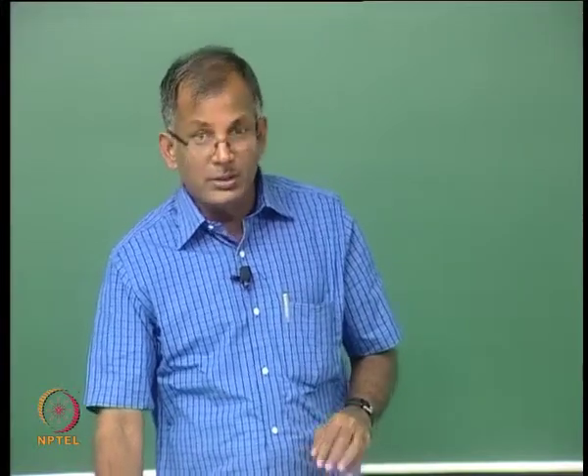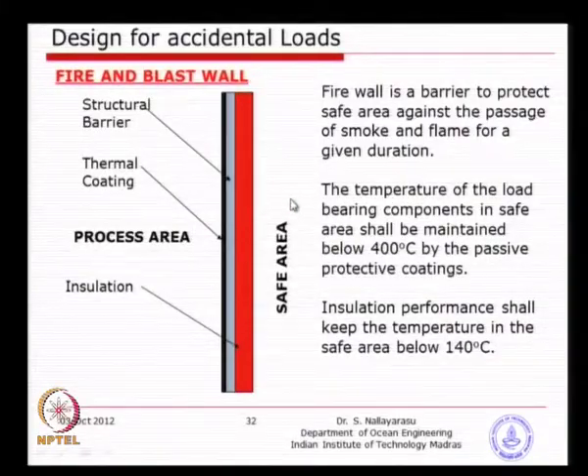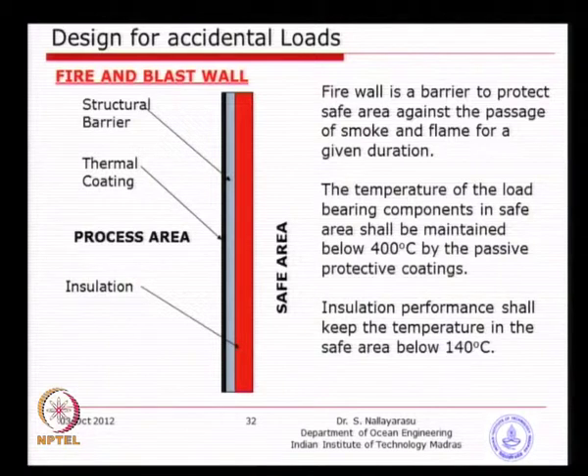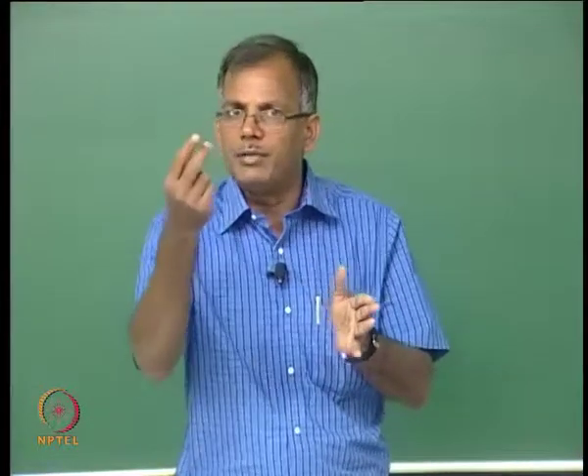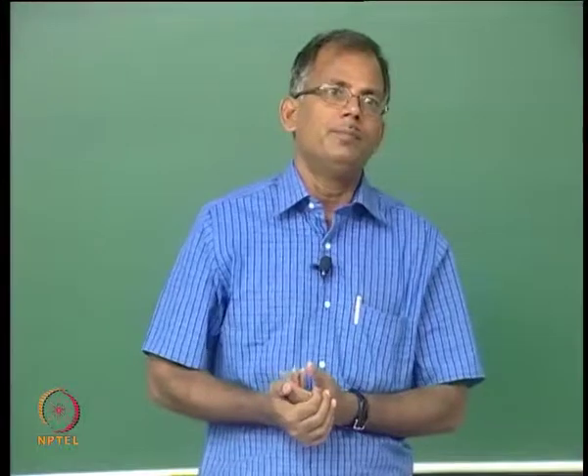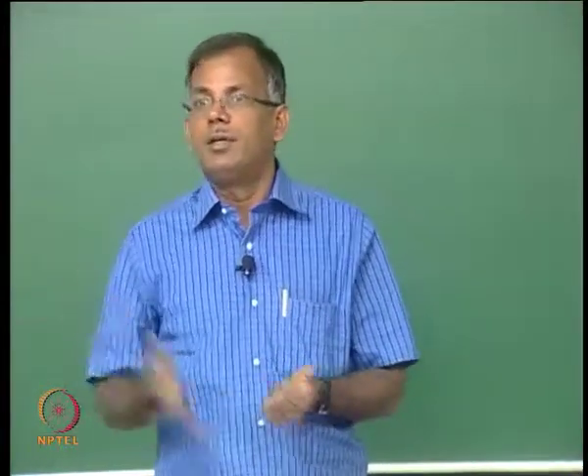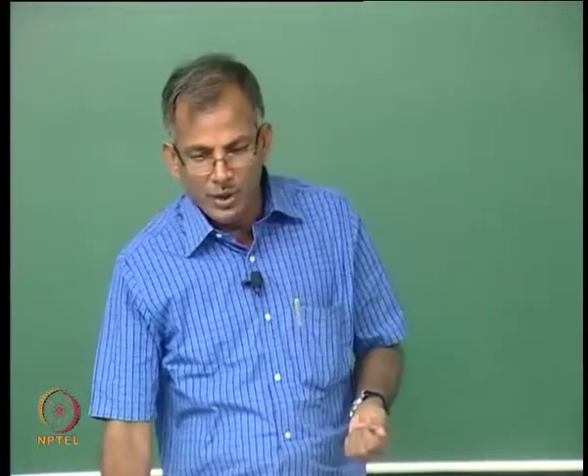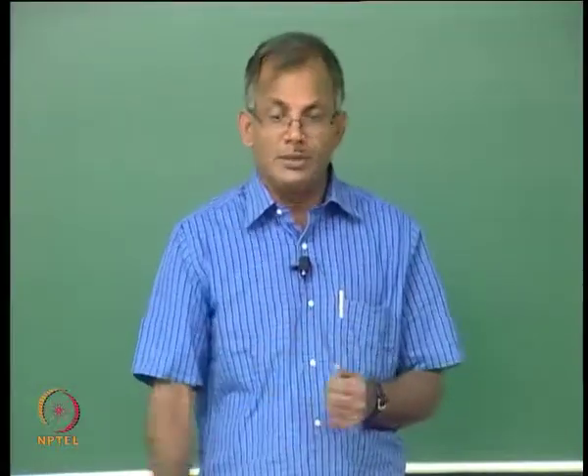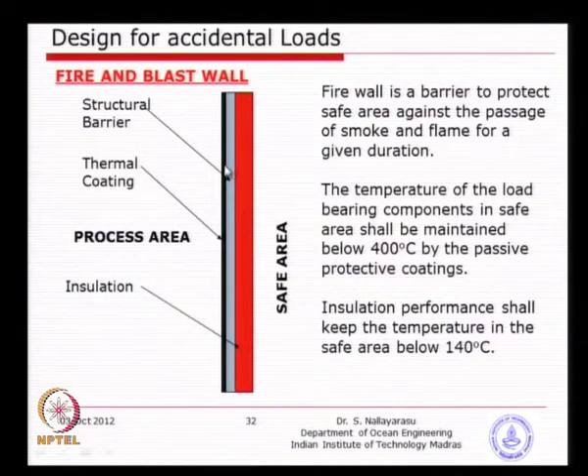Even if the steel is at 400 degrees, you do not want occupants in direct contact with 400 degrees — nobody can sustain that, since we normally live at less than 40 degrees. The insulation on the inside limits the temperature so occupants can sustain for a slightly longer period. At 400 degrees you can only stay for a minute or two, but at 40 degrees you can stay for another half hour before evacuation. The insulation must be placed on the inside — if placed before the steel, the temperature would destroy the insulation itself.